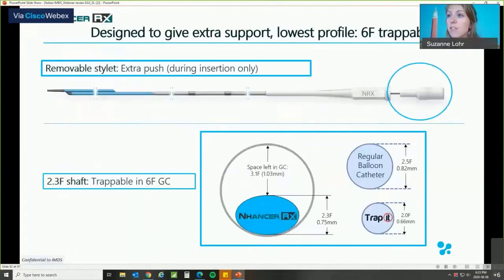The Nhancer Rx is designed to give extra support while keeping the lowest profile in order to make it 6-French trappable. The Nhancer Rx gains extra push from a removable stylet that can be inserted into the over-the-wire lumen of the catheter. So when the device is advanced with a guide wire inside the tip through the rapid exchange lumen, the over-the-wire lumen is free and the stylet can be inserted in this over-the-wire lumen. This gives a lot of extra support, but you don't lose any profile because of that.